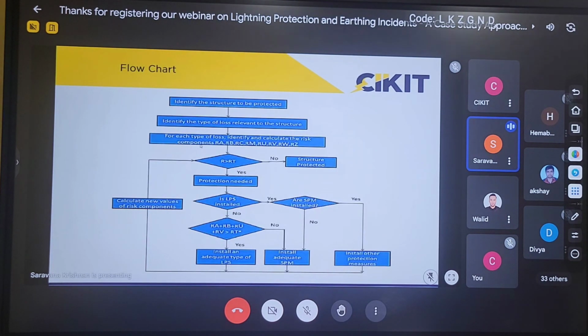If the value of R is lesser than RT, then the risk due to lightning will be lower on that particular structure. So if I am performing the calculation and even without any external protection measures like installing a lightning protection system, the risk due to lightning is lower, in that particular case, a lightning protection system is not mandatory for my building or structure. If a lightning protection system is not mandatory, it means that even if lightning strikes my structure, the damage will be lower, and we can manage.